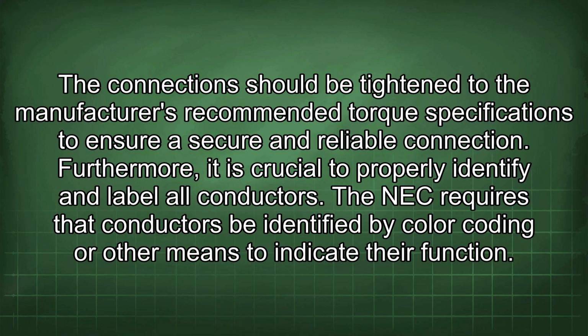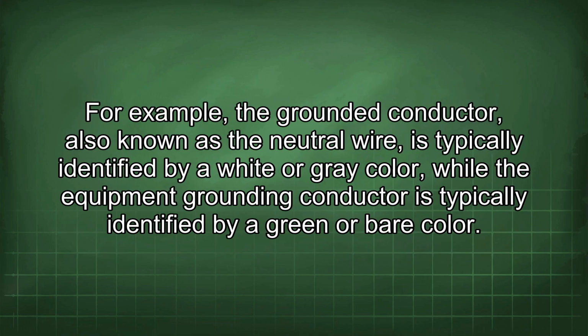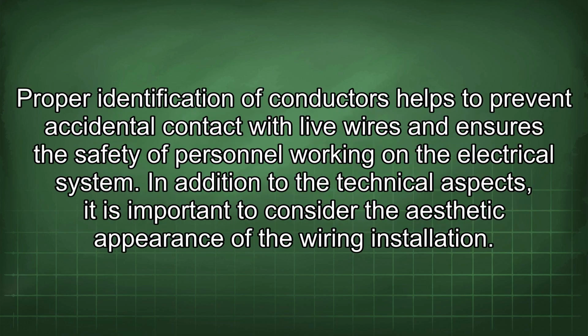Furthermore, it is crucial to properly identify and label all conductors. The NEC requires that conductors be identified by color coding or other means to indicate their function. For example, the grounded conductor, also known as the neutral wire, is typically identified by a white or gray color, while the equipment grounding conductor is typically identified by a green or bare color. Proper identification of conductors helps to prevent accidental contact with live wires and ensures the safety of personnel working on the electrical system.